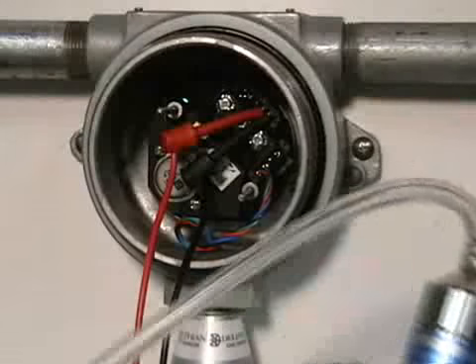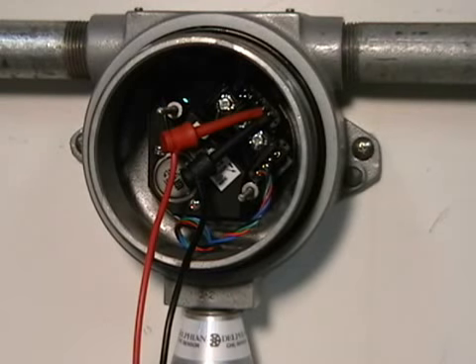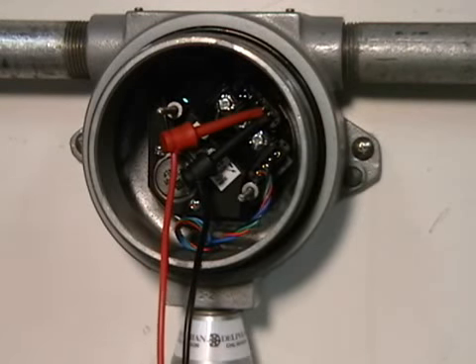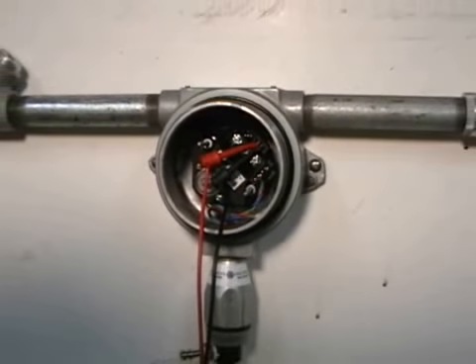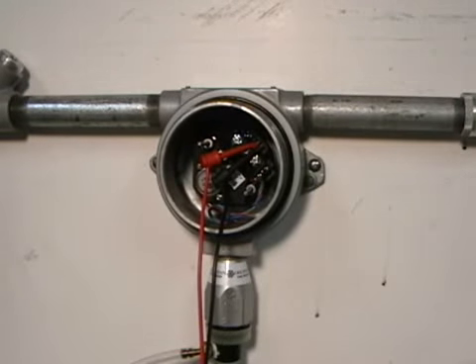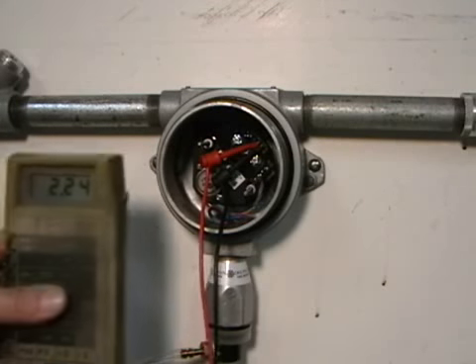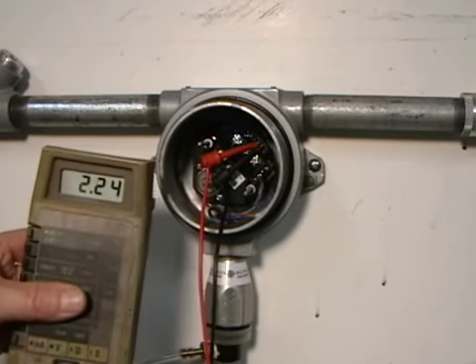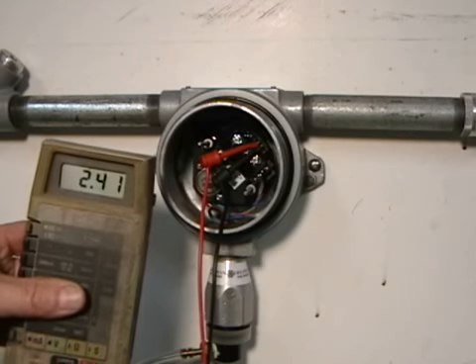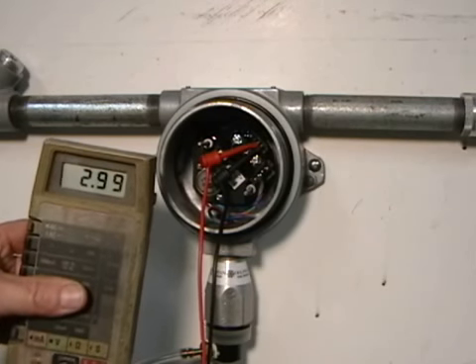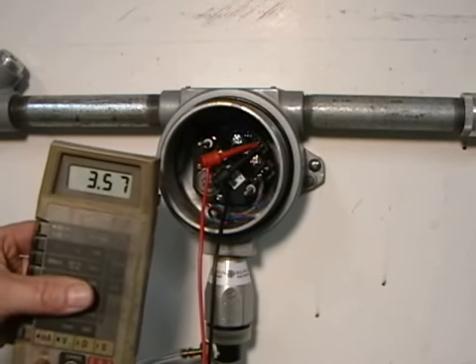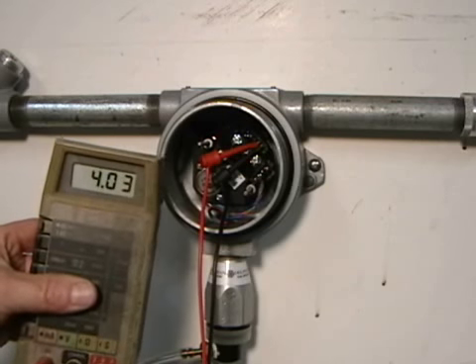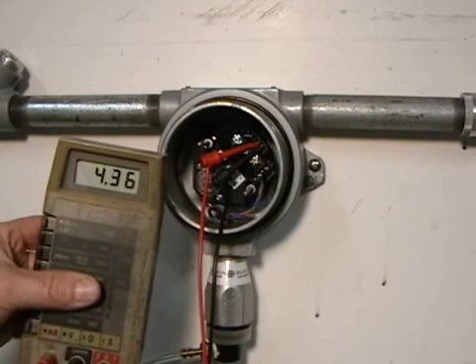Now you can snap on the sensor gas connector and supply a 50% LEL gas in air mixture to the sensor. This will verify if the sensor has enough life left to perform its function. A change in span from its zero reading, in this example 2.24 milliamps, to its span reading is called delta change and should be approximately 3 to 3.5 milliamps on a new sensor to as little as 0.5 milliamps on an aged or poisoned sensor.